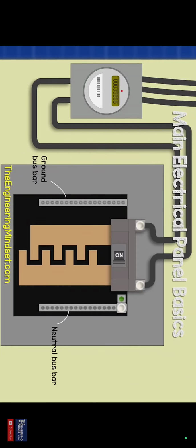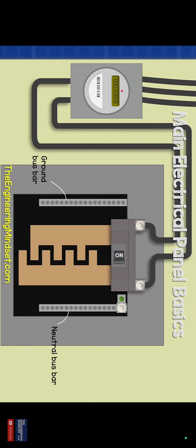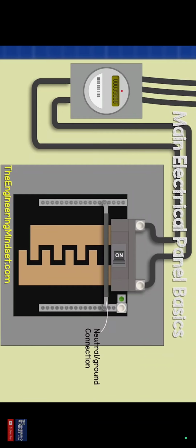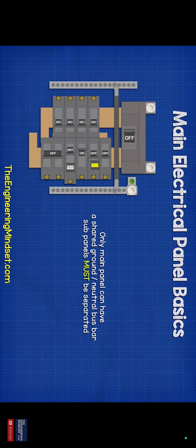Inside the panel, we also have a neutral and ground bus bar. This is basically a strip of metal with lots of holes and screws in it on either side of the panel and connects a bar between them. That way we have a shared neutral ground bus bar. Sub-panels must have their bars separated, but that's a topic for a separate video.